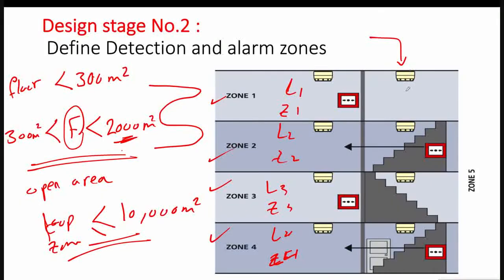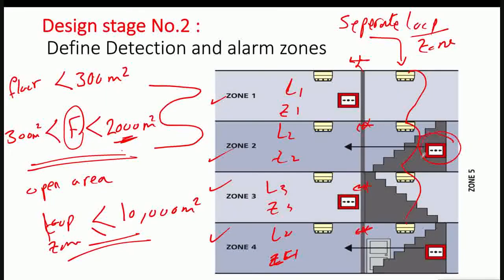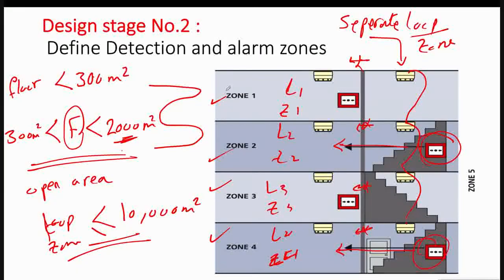An important consideration: all stairs on all floors should be on a separate loop or zone. The stairs zone connects all stairwells across all floors and is not connected to the floor zone. However, all manual call points on the stairs should be connected to the floor loop.